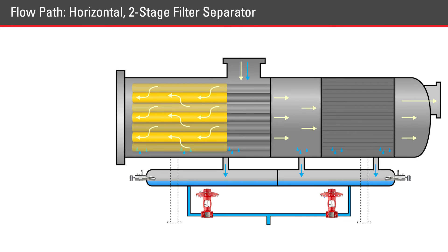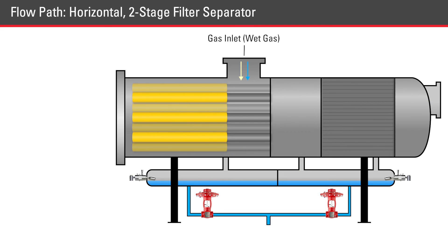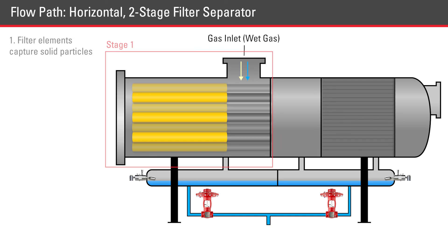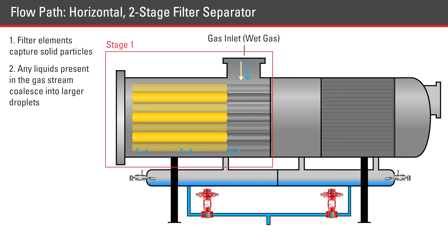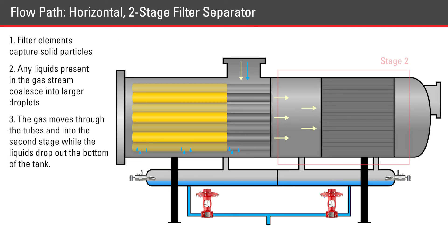This rendering shows the flow of natural gas through a horizontal, two-stage filter separator. As natural gas enters the unit, the first stage of filter elements captures solid particles. In this rendering, coalescing filters are used. These allow any liquids present in the gas stream to coalesce into larger droplets. The gas moves through the tubes and into the second stage while the liquids drop out to the bottom of the tank.